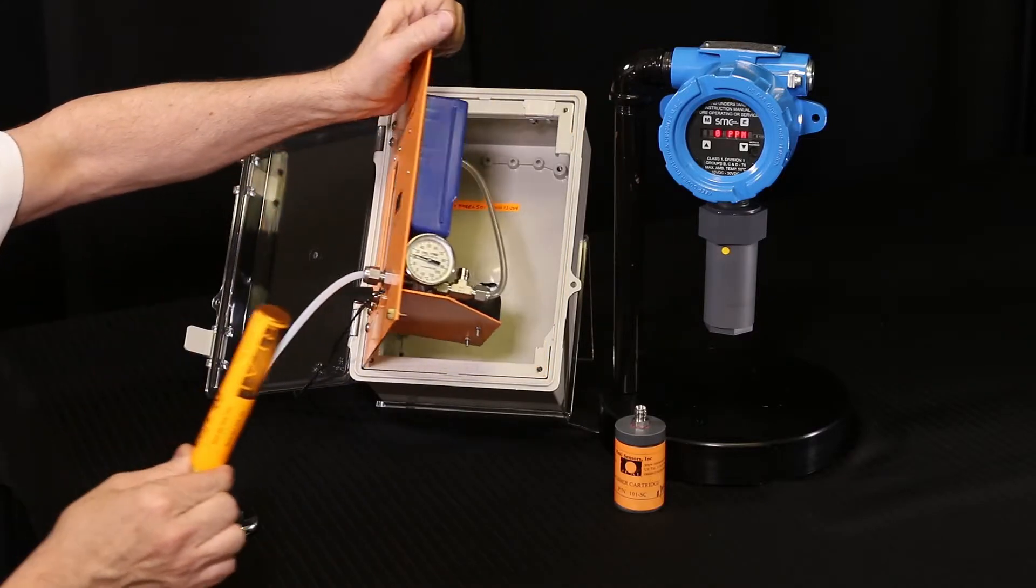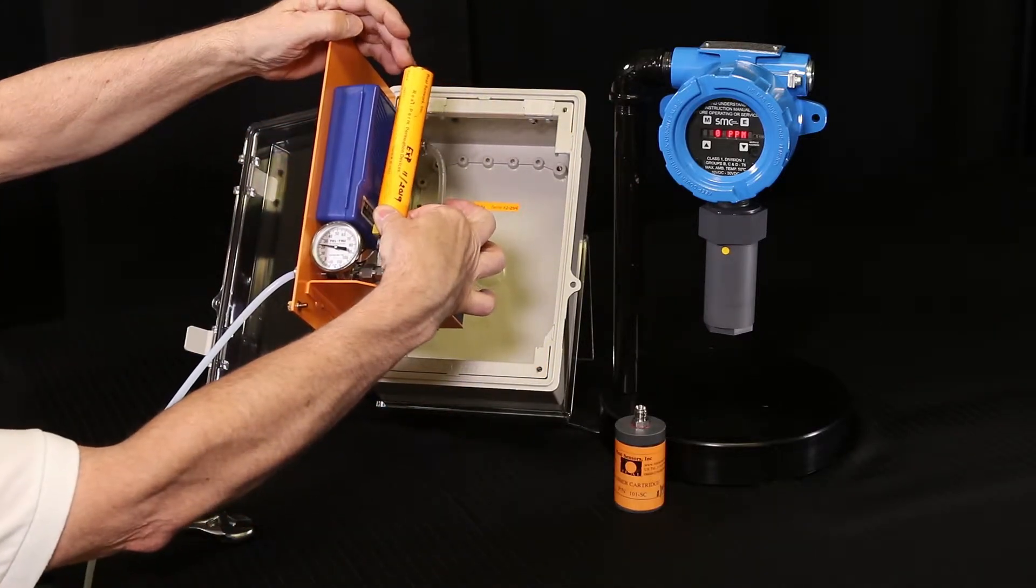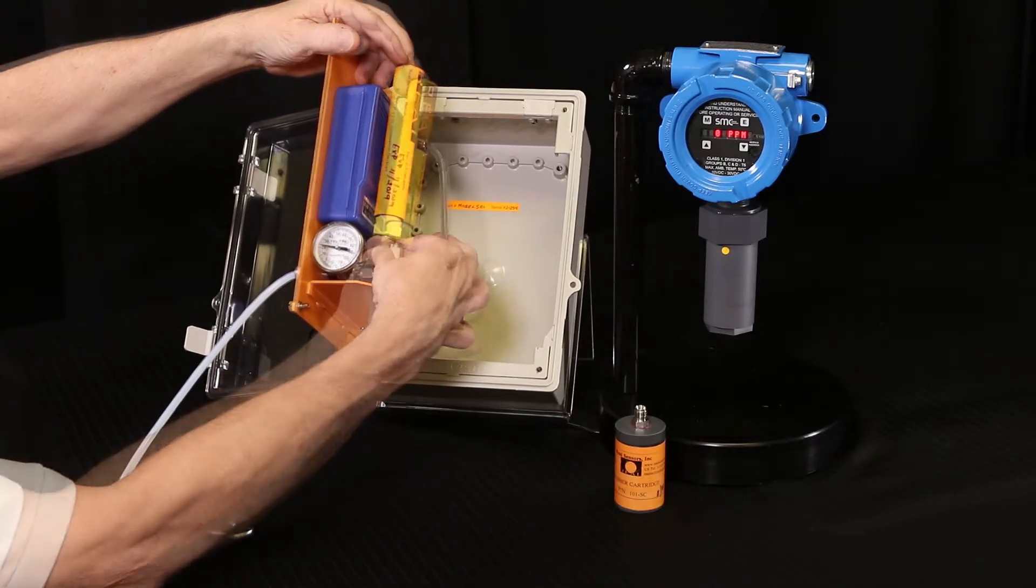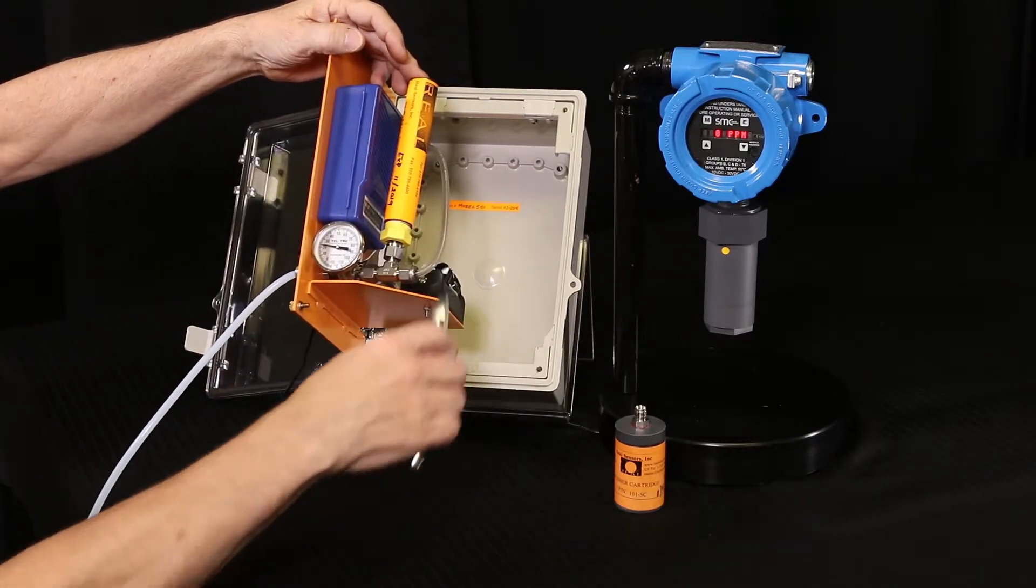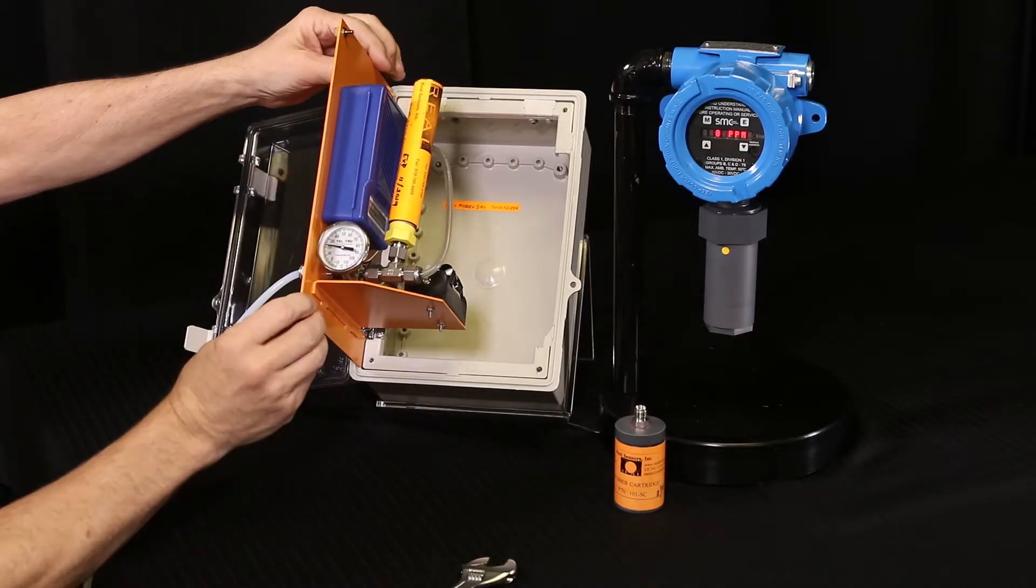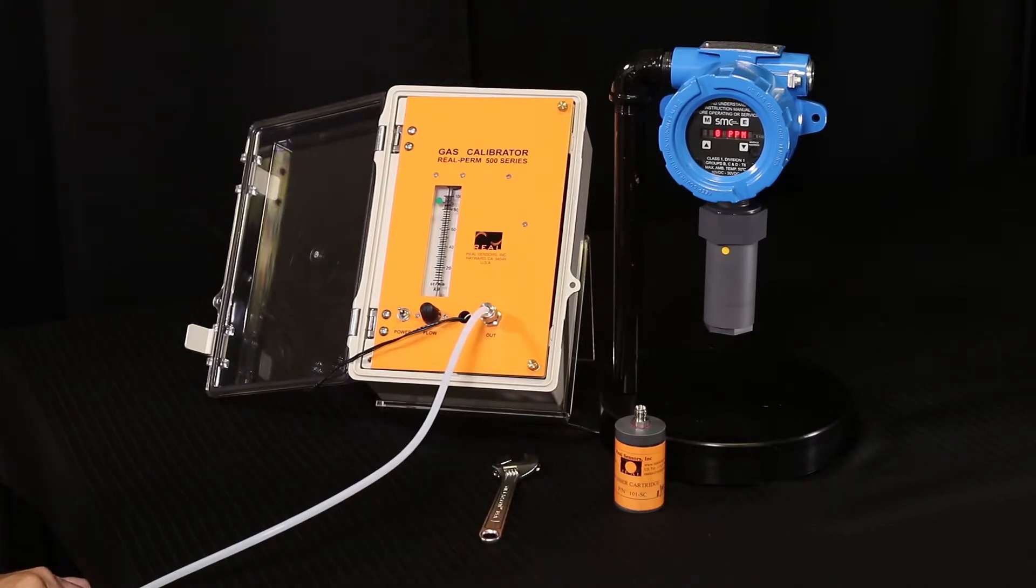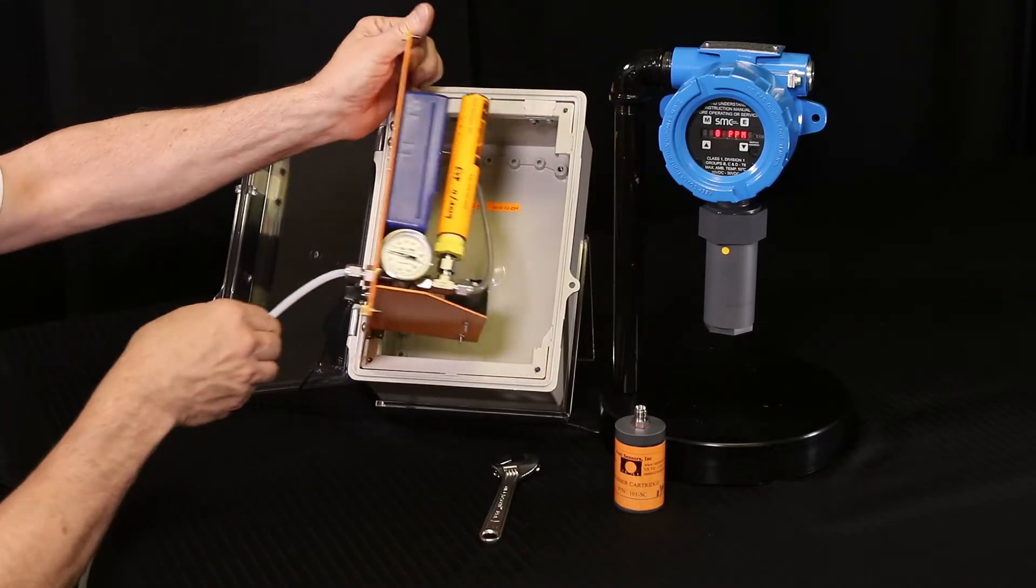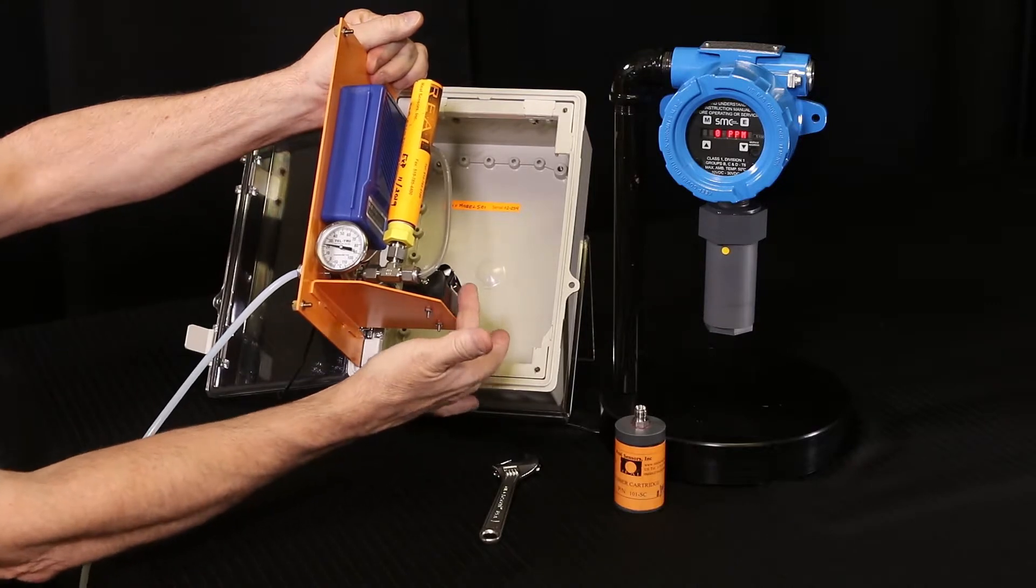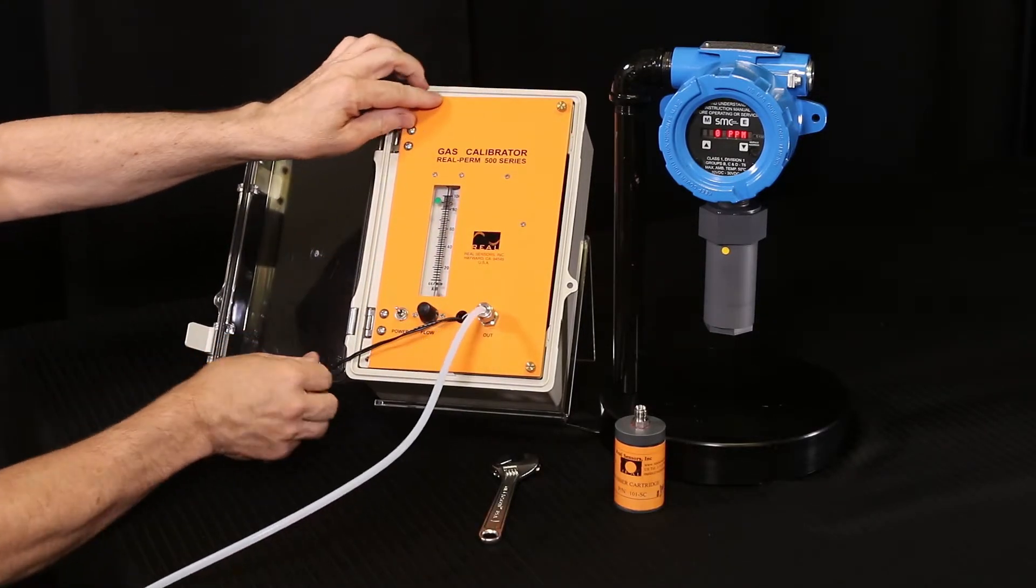First, install the tube into the quarter-inch tube T inside the calibrator enclosure using the 9/16 inch wrench. Tighten snugly. Next, verify that the D cell battery for the pump is installed and operational. Replace if needed. Please note that the unit is used for demonstration and has the battery replaced with a power supply.